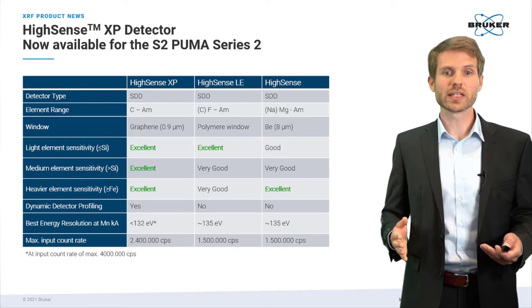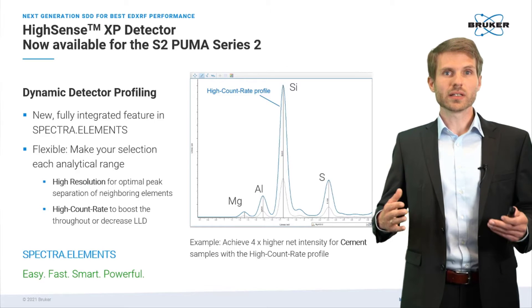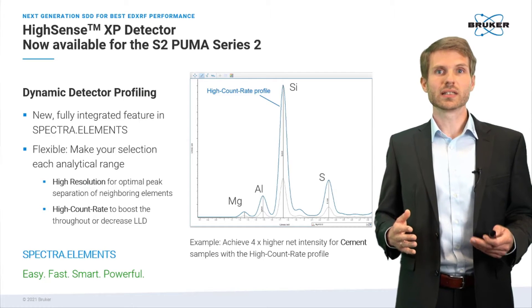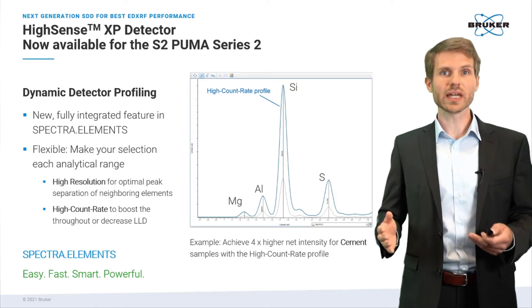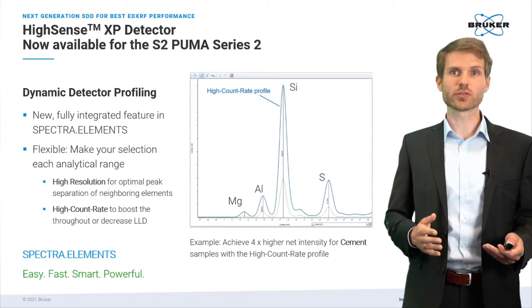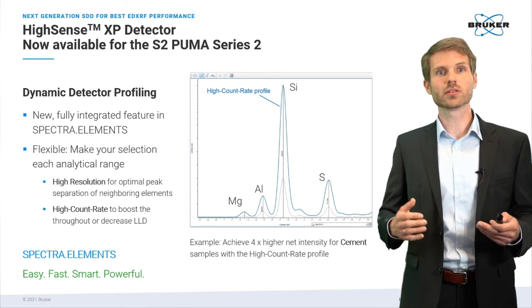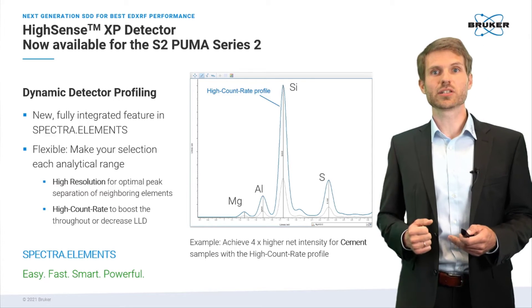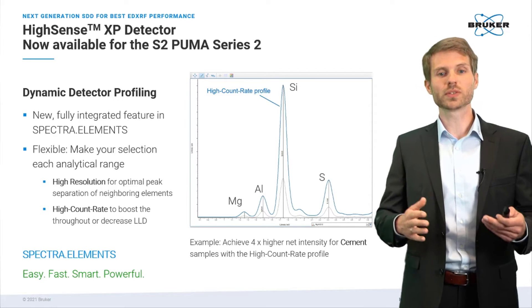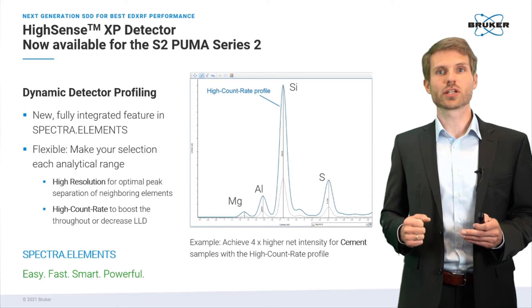Let me explain what this means in real life. The dynamic detector profiling is a fully integrated feature in the software SPECTRA.ELEMENTS. This means when you set up a method, you can select for a given element of interest or given voltage whether you want to boost the count rate, enhance the energy resolution, or use the optimized default setting — a medium balance of both.